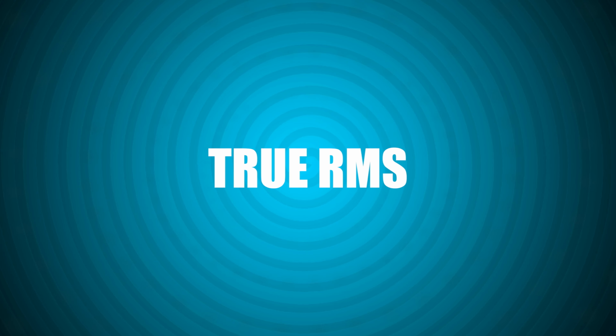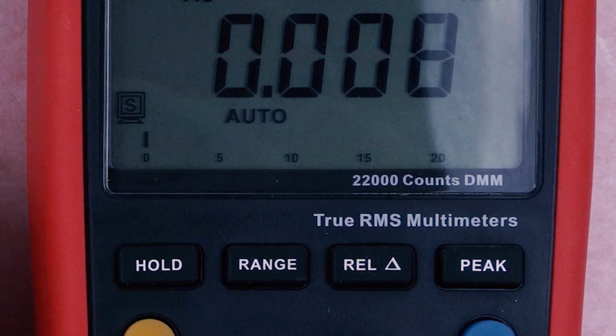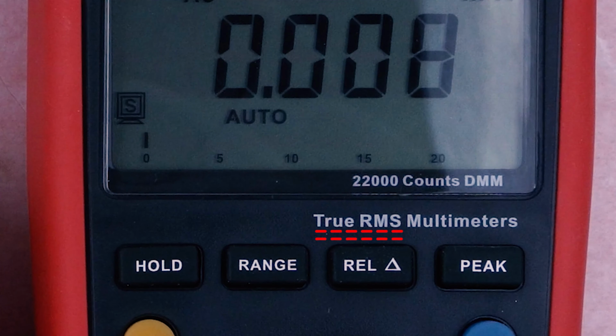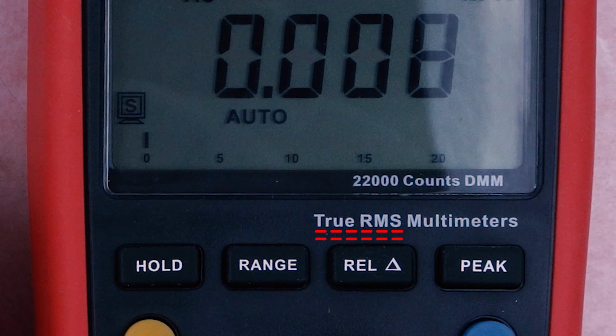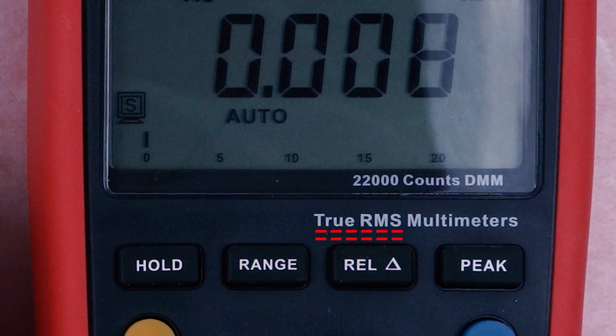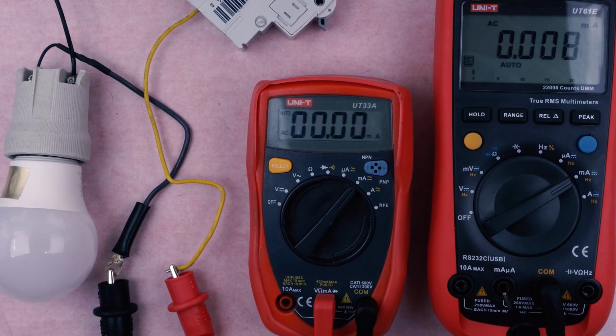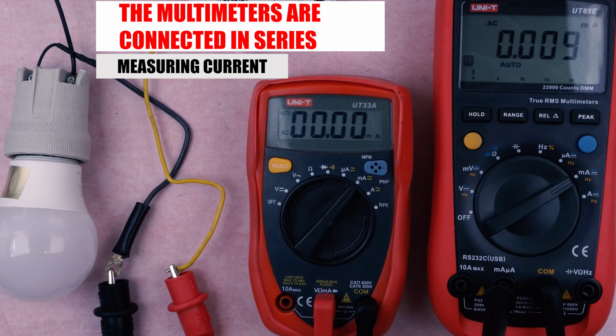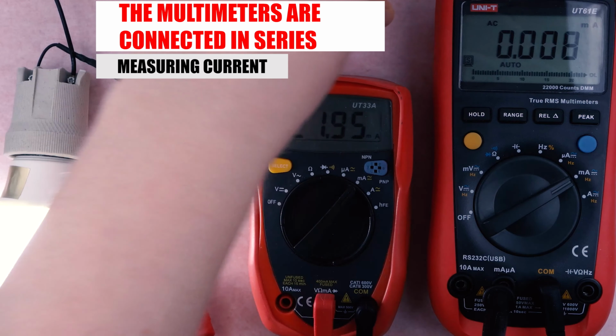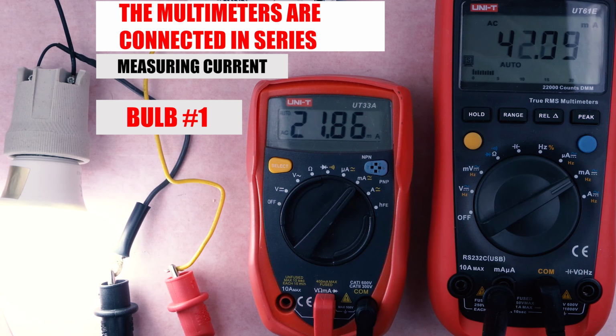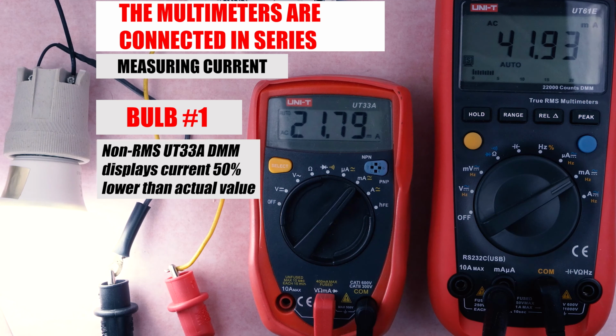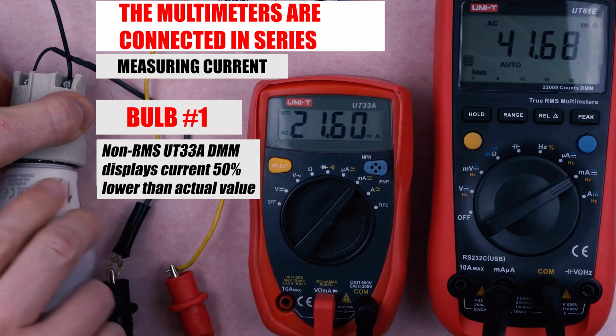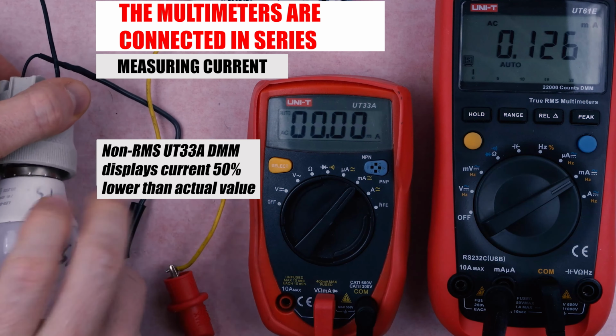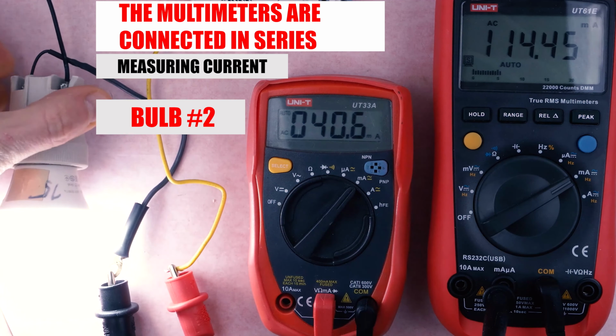True RMS. You have probably noticed that some DMMs proudly bear the True RMS logo. Usually this feature is only present in expensive devices ranging from $100 and up. In essence, True RMS serves the purpose of properly measuring AC signals with imperfect non-sinusoidal waves. For example, if you're up to measuring current or power consumption of an AC LED light bulb, you simply cannot do it with a non-RMS multimeter, because your measurement will be way off.